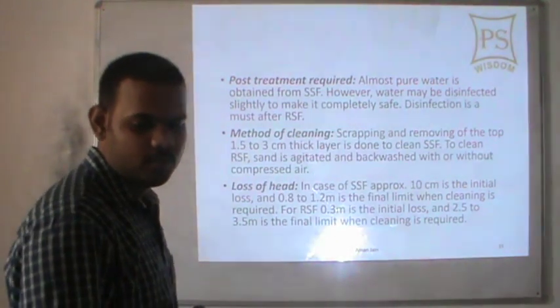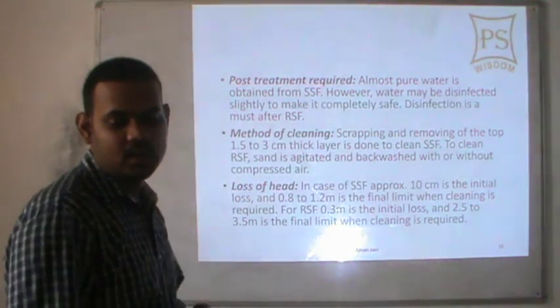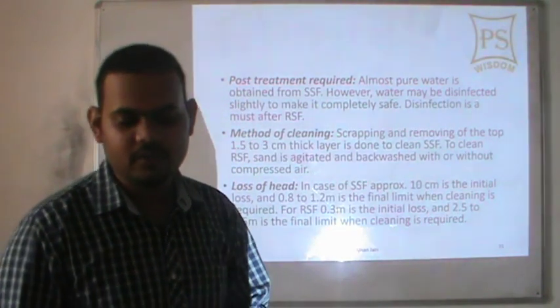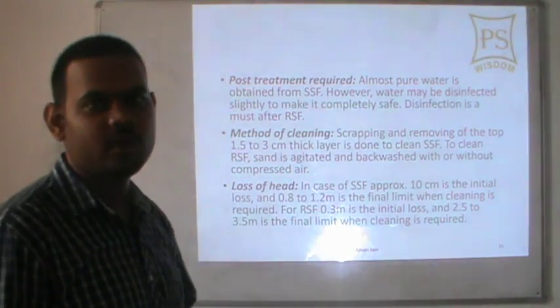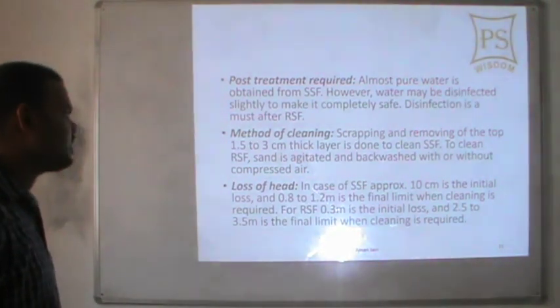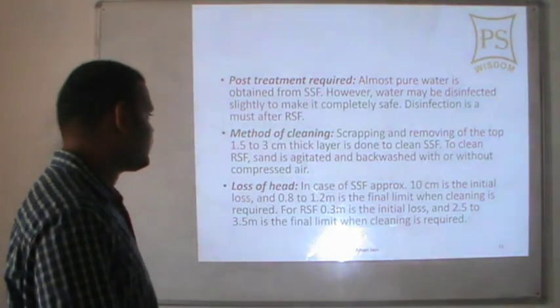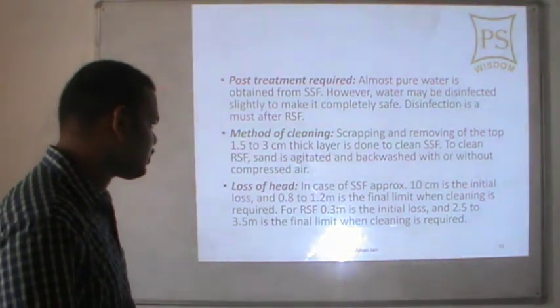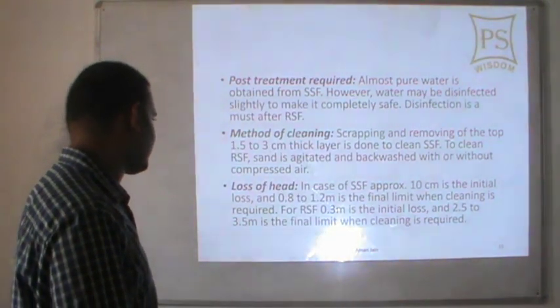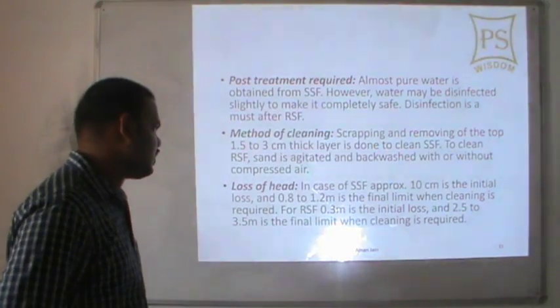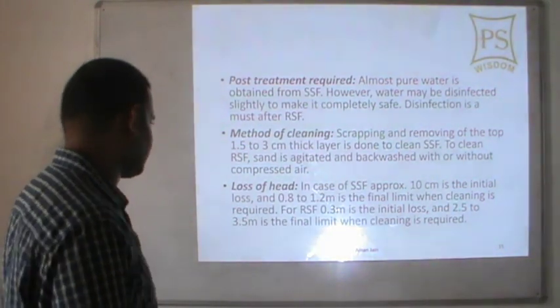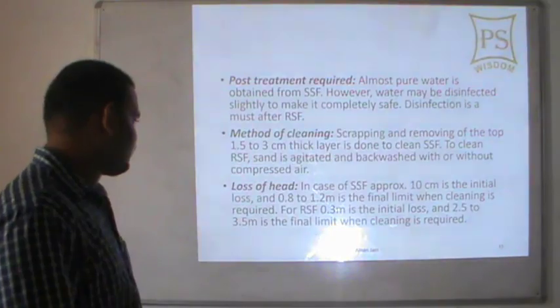Post treatment: almost pure water is obtained from slow sand filters; water may be disinfected slightly to make it completely safe. In RSF, disinfection is a must. Method of cleaning: in SSF, scraping and removing the top 1.5 to 3 cm thick layer is done. To clean RSF, sand is agitated and backwashed with or without compressed air. Loss of head in SSF: approximately 10 cm is the initial loss, and 0.8 to 1.2 meters is the final limit when cleaning is required.